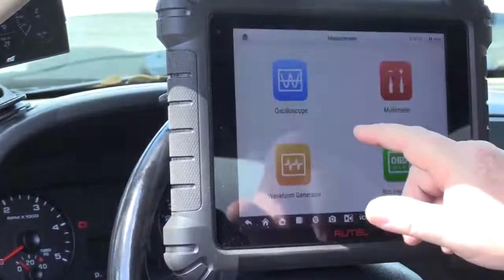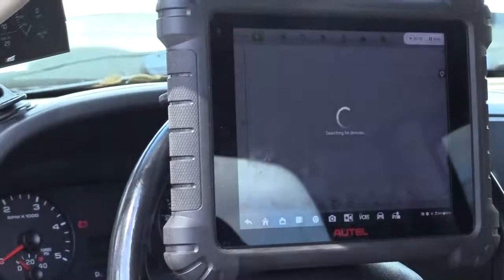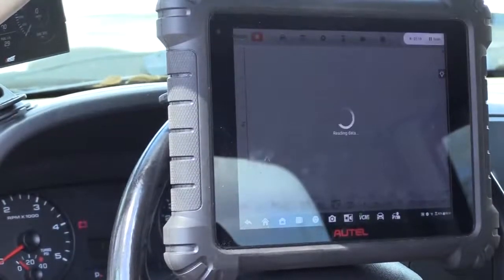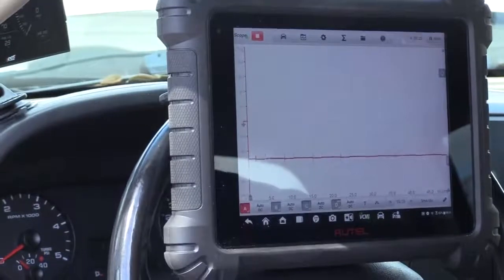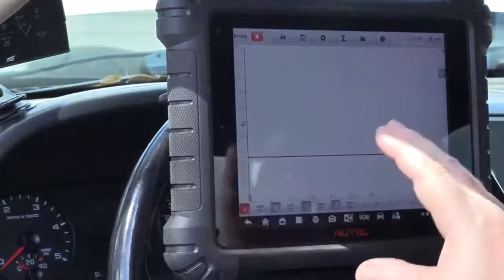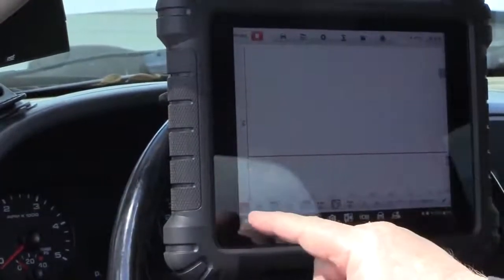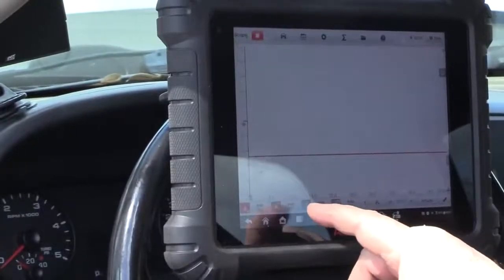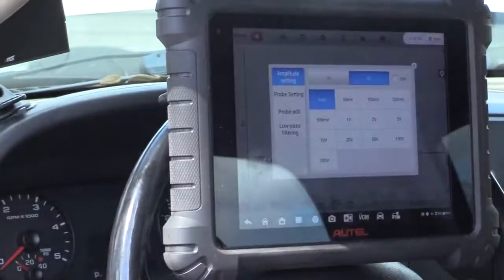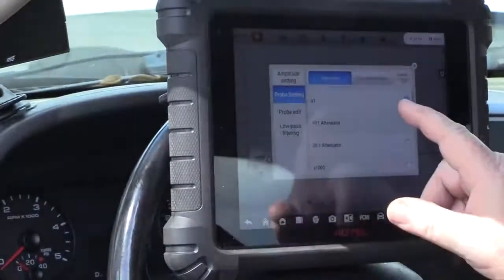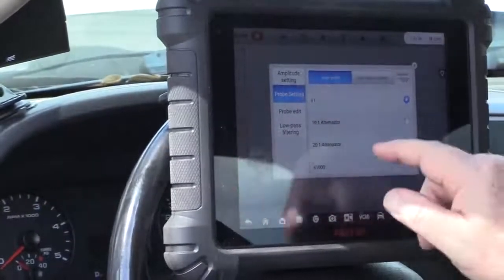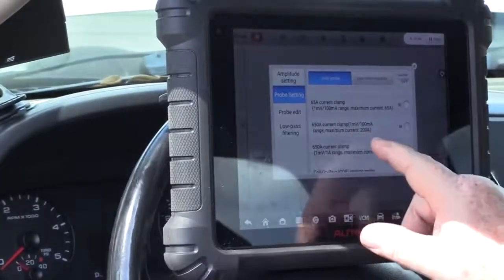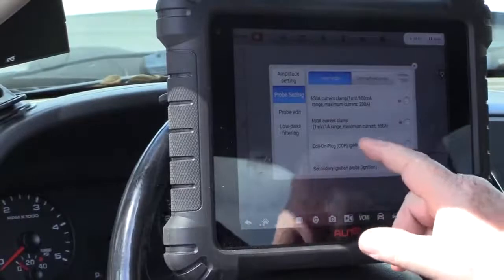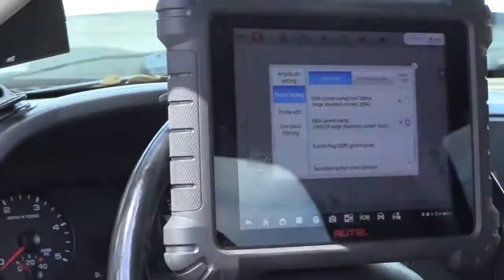First we're going to select the scope from the menu. Let it connect to the VCI. And then we're going to set up our channels. Now remember, we have the high amp probe on channel A and just a regular direct lead on channel B. So let's set that one up first. Because we're using a high amp probe, we have to let the scope know that we're doing that. So we've used the 600 amp current clamp, and we've got it set on the 1 millivolt equals 1 amp range. So we're going to make that selection.